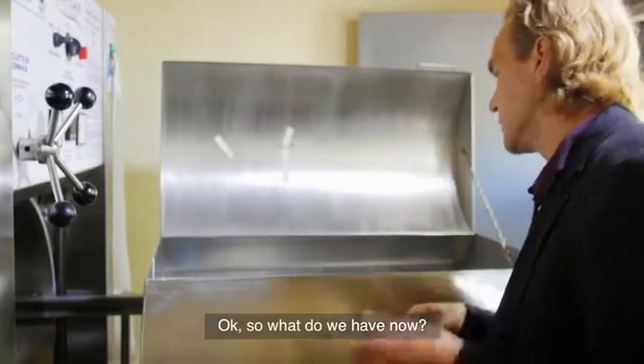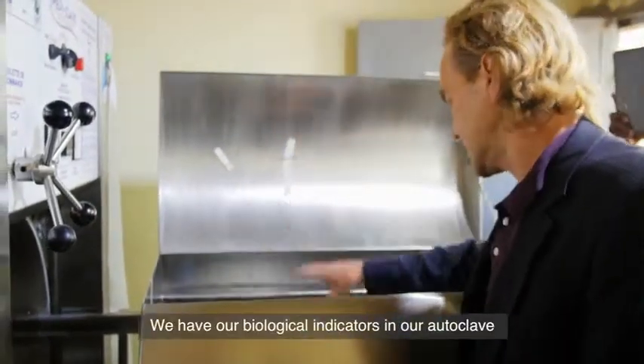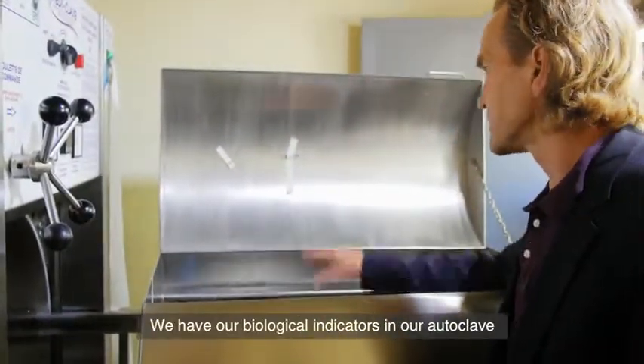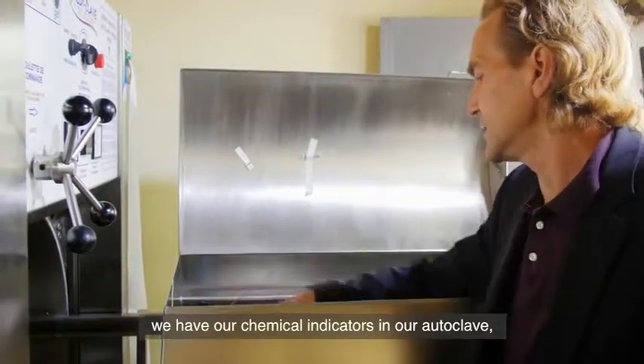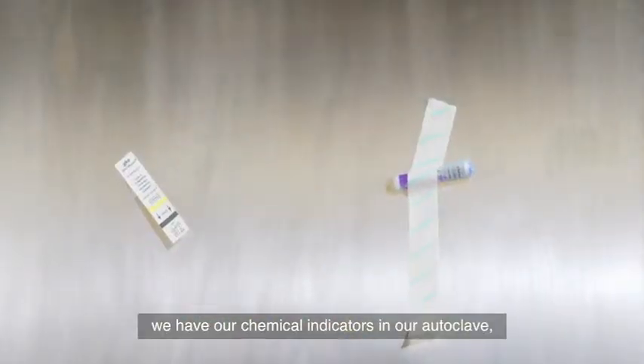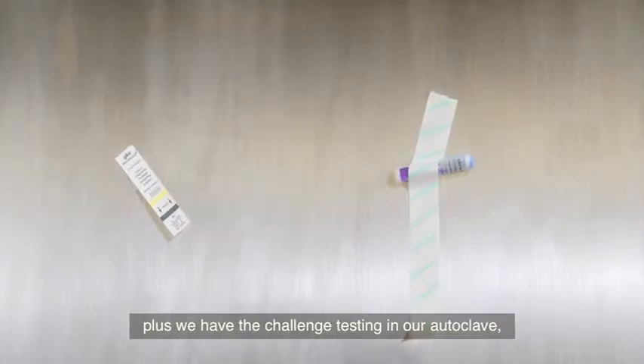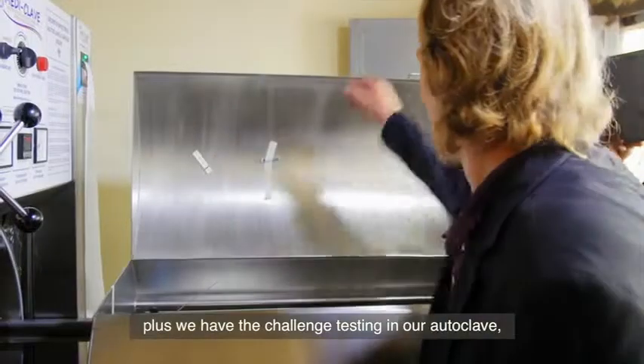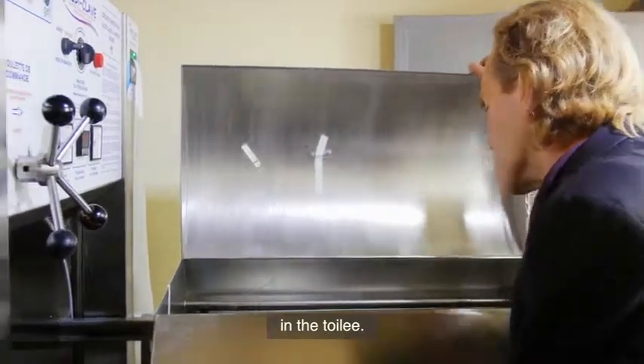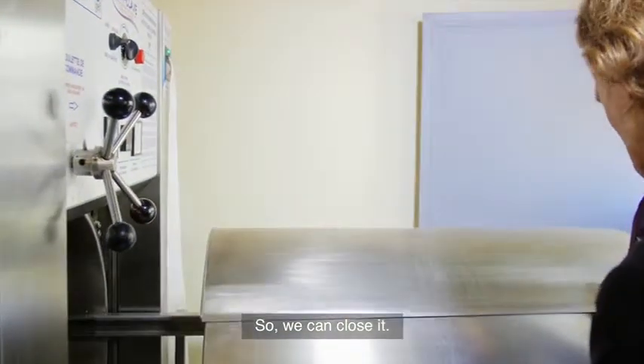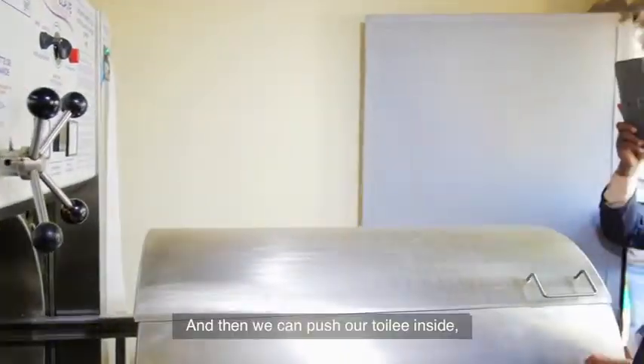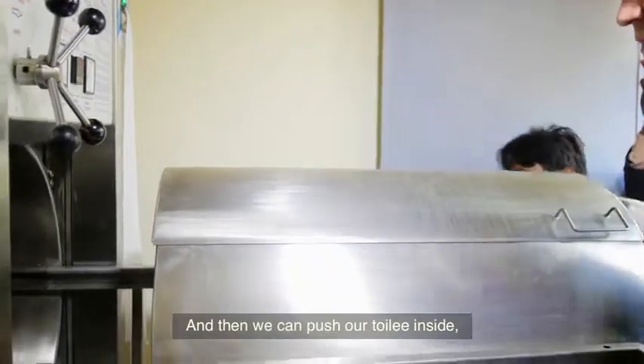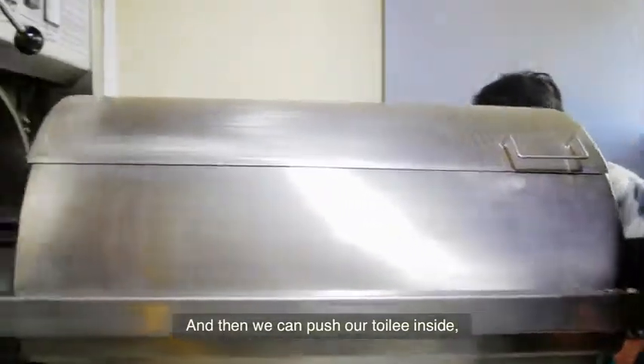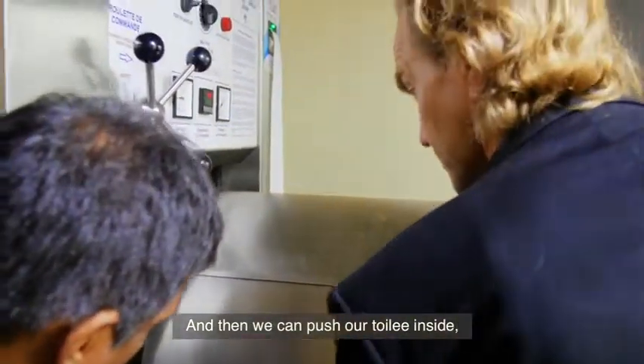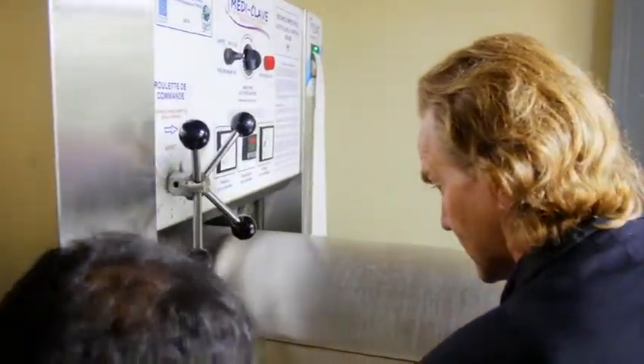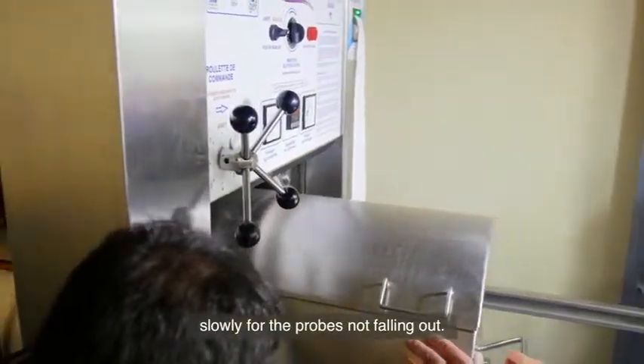Okay, so what do we have now? We have our biological indicators in our autoclave. We have our chemical indicators in our autoclave, plus we have the challenge testing in our autoclave in the trolley. So we can close it, and then we can push our trolley inside. Slowly, so that the probes are not falling out.